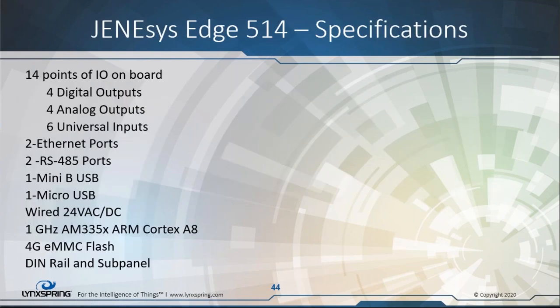Here are the specifics of the points: there are 4 digital outputs with the same specifications as the 534, and the analogs—the six universal inputs—share the exact same specifications as the 534. So literally it's a 534 cut down by about two-thirds. It has the same Ethernet ports, RS-485 ports, USB ports, and power requirements, and internally it has what we call a Lynxspring Smart Module, which encapsulates the Cortex processor, flash memory, and is where Niagara resides.